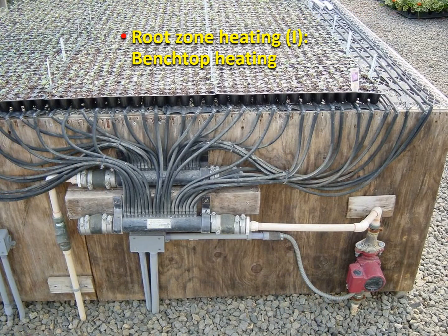Root zone heating systems deliver heat energy to the immediate vicinity of the crop. This reduces heat losses and in some cases allows growers to maintain lower air temperatures, resulting in further reductions in heating demand. Many crops respond very favorably to root zone heating, and the heat is typically delivered very uniformly.